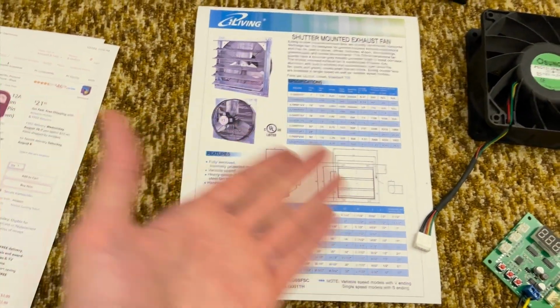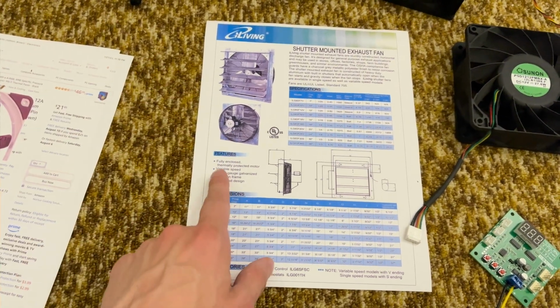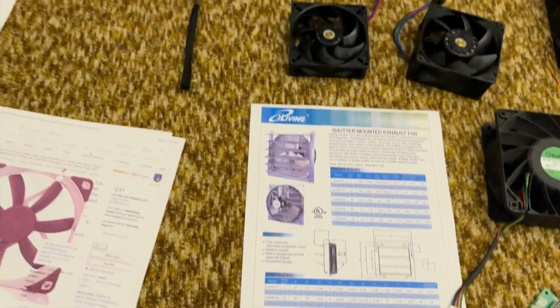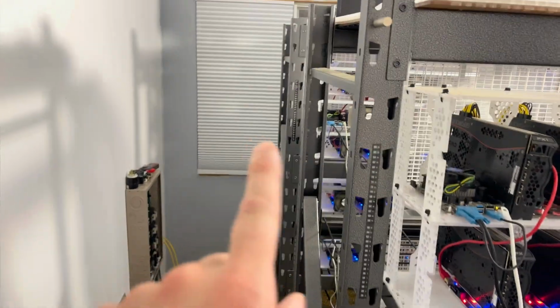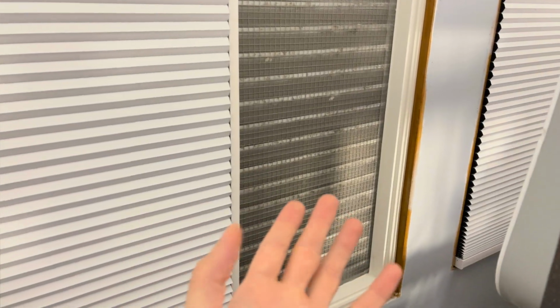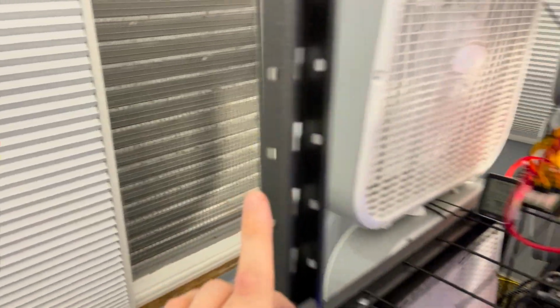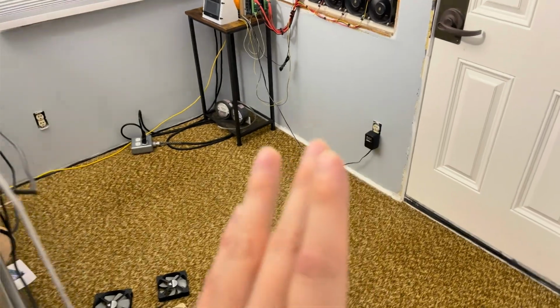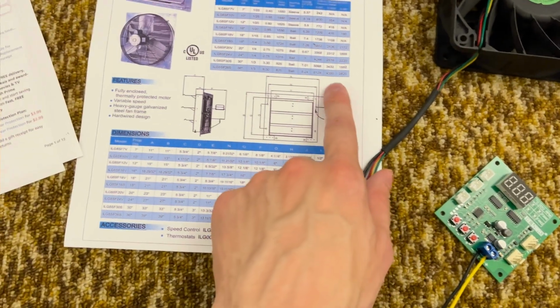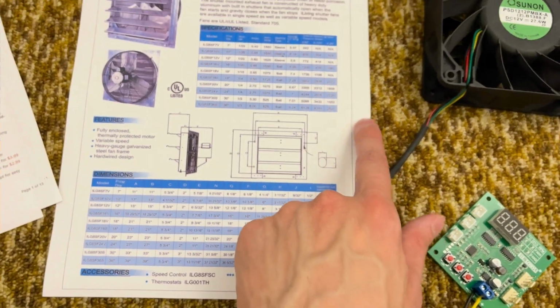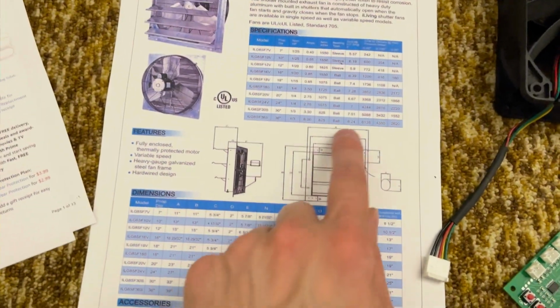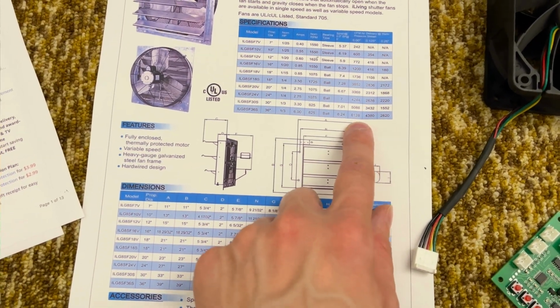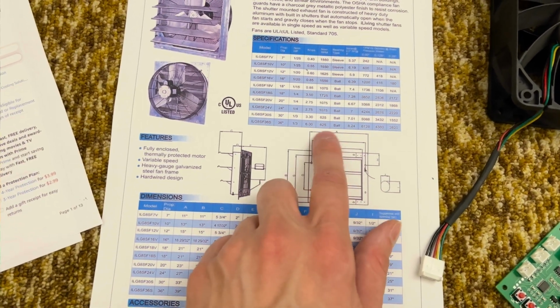When you think maybe your calculations say one's enough, inevitably you might need two or even three. And this is my environment here with no filters there. It's just a screening. So I still get some little bugs and stuff like that. Mostly not an issue. However, if you really want good filtration, they could add a lot of static pressure. A good filter could add easily 50 pascals or 100 pascals. Which on a fan like this is way off the chart. I'd be pushing probably 1,000 CFM or less on this fan that says 6,000. So that's a big issue. Totally screws up your efficiency here.